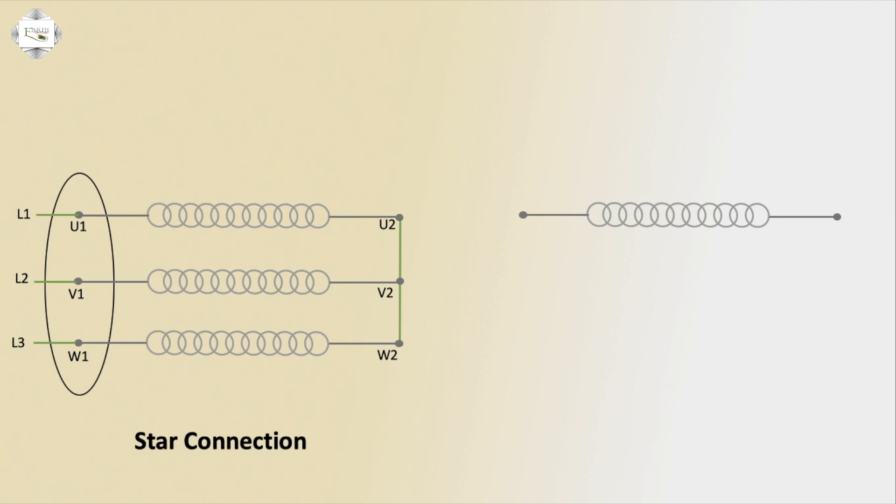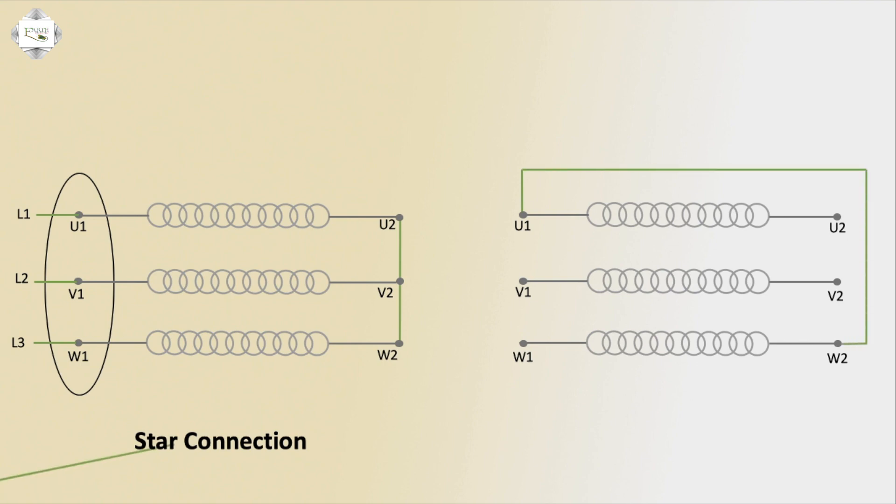For 3-phase delta connection, first U1 connects to W2. Then V1 connects to U2. Finally W1 connects to V2. This forms the delta connection.